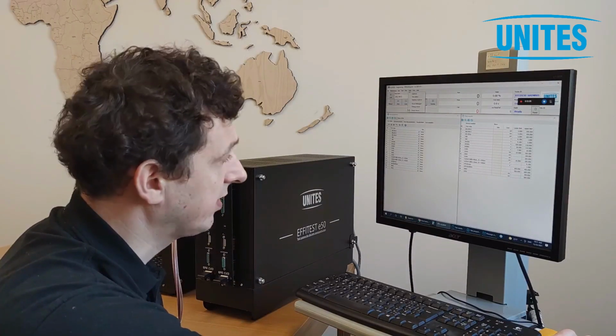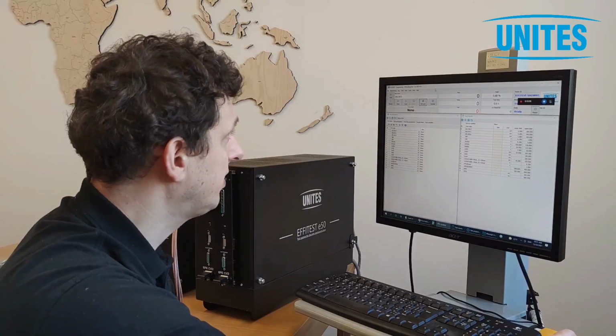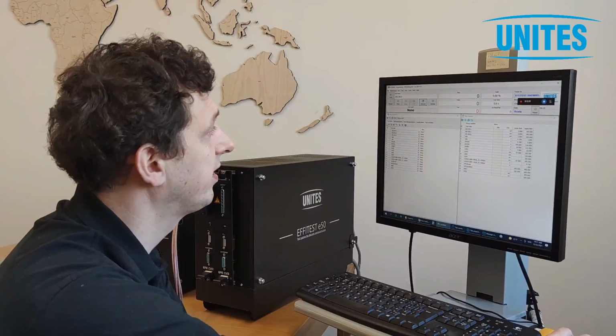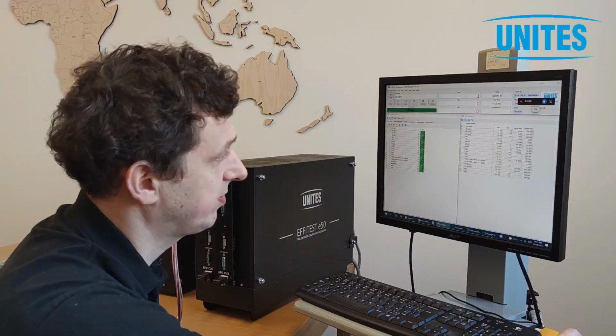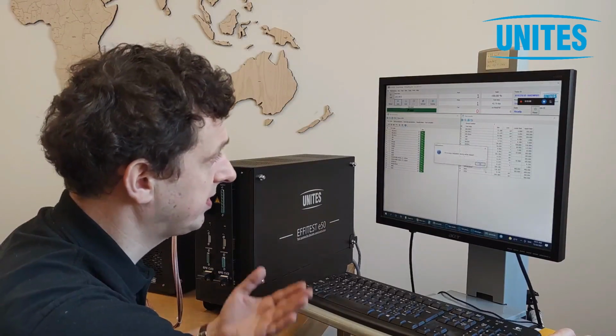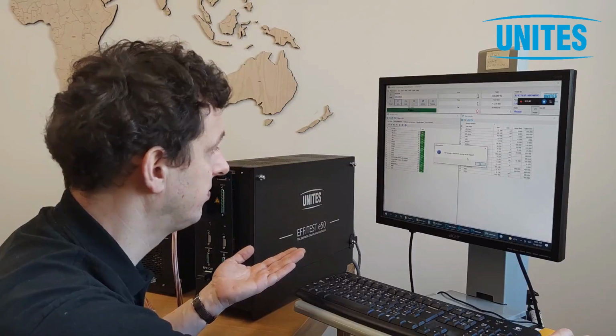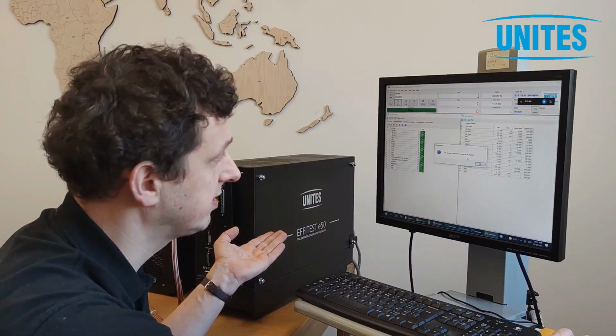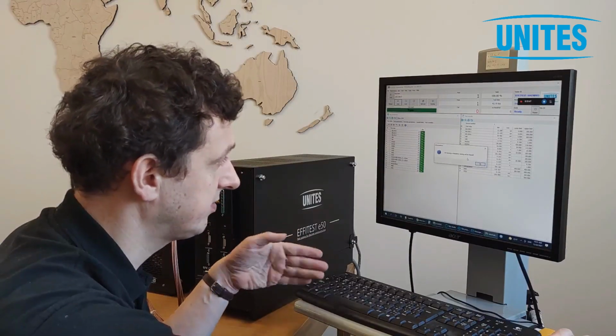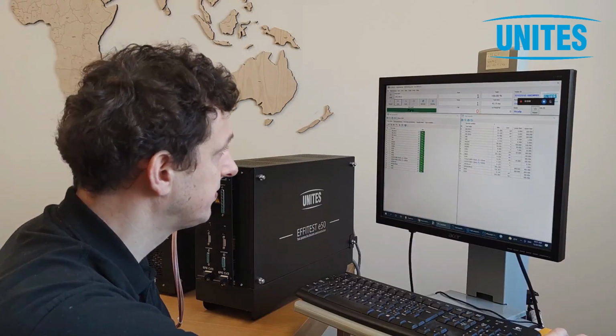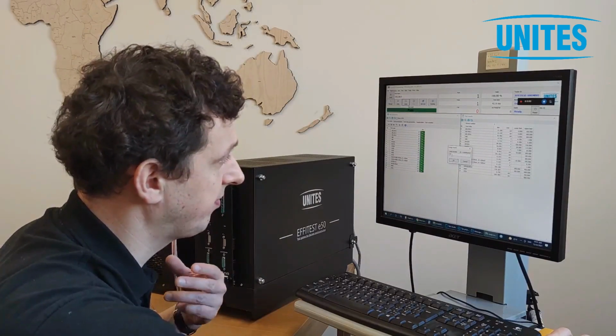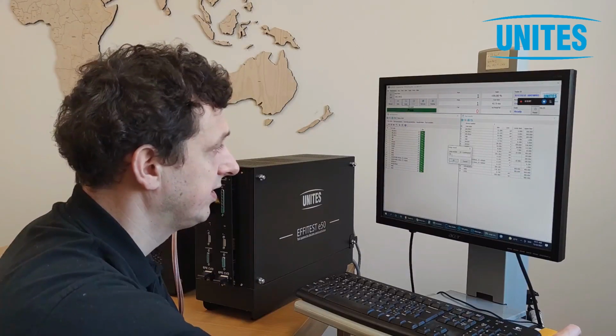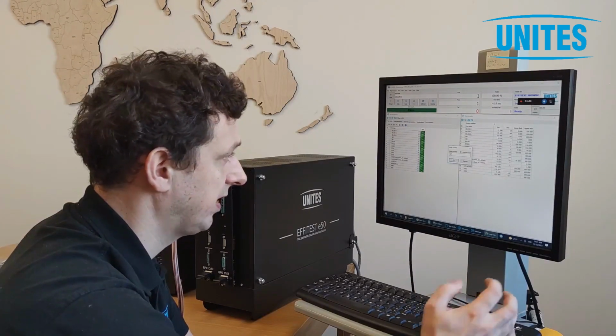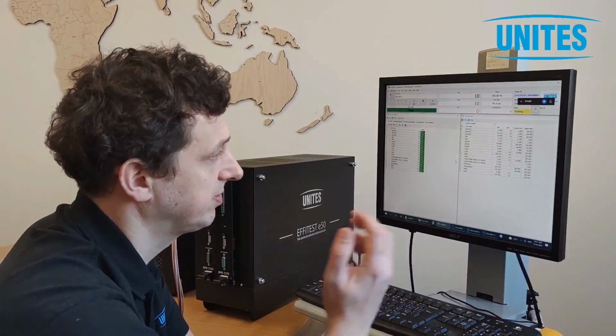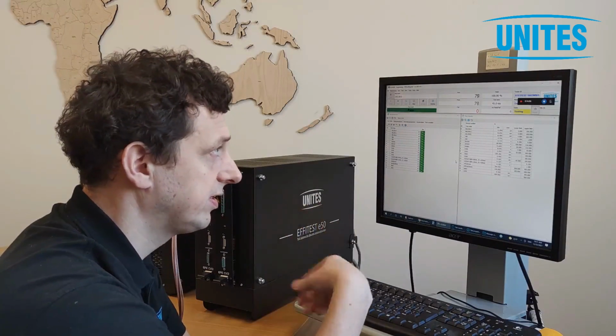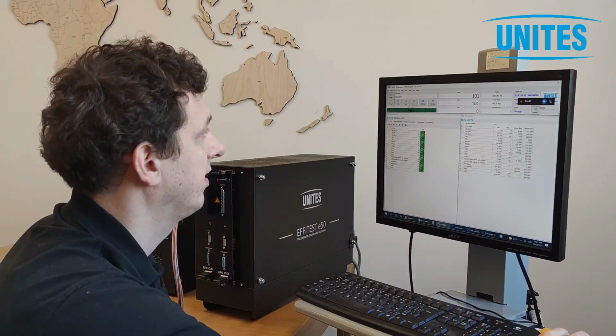Let me tell you more about other options which we have here. First, there are 3 modes which we can run. Manual is one run. Automatic is with the handler. When the handler is connected, it's waiting for the start of test signal, and then for the end of test signal, and of course it can have other signals. And loop means that I'm making the testing on the same device, let's say 100 times, 1,000 times. So this is one DUT constantly tested, retested again and again.